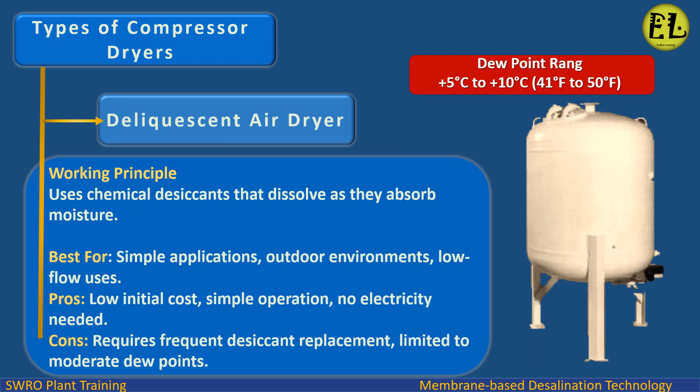Deliquescent air dryers. Working principle: uses chemical desiccants that dissolve as they absorb moisture. Best for simple applications, outdoor environments, and low flow uses. Pros: low initial cost, simple operation, no electricity needed. Cons: requires frequent desiccant replacement, limited to moderate dew points. Dew point range: 5°C to 10°C (41°F to 50°F).